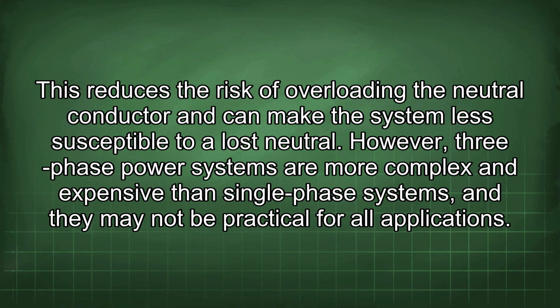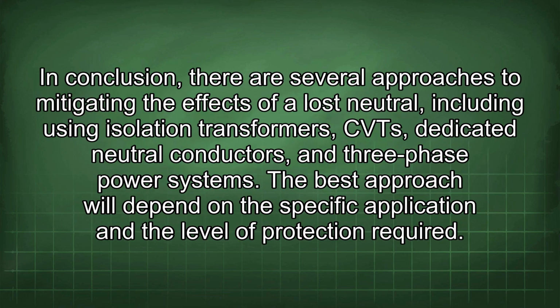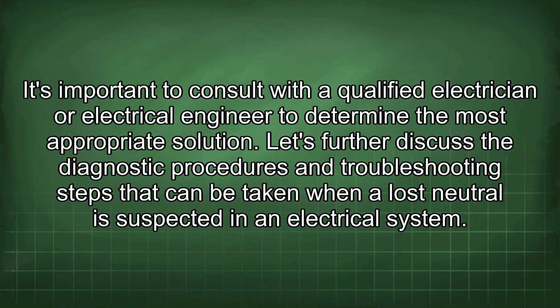the electrical panel. Another approach is to use a three-phase power system instead of a single-phase system. In a three-phase system, the neutral current is typically much lower than in a single-phase system. This reduces the risk of overloading the neutral conductor and can make the system less susceptible to a lost neutral.